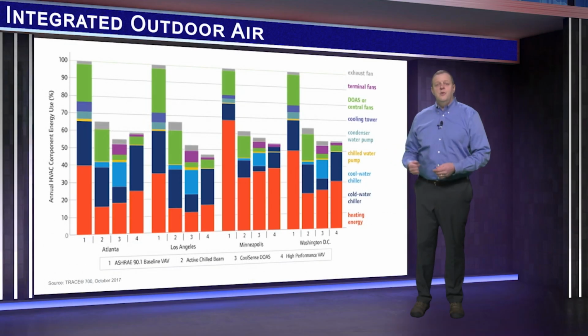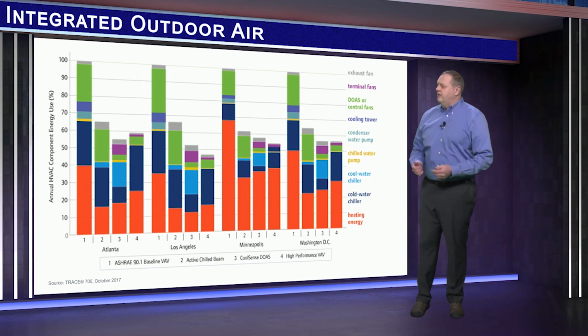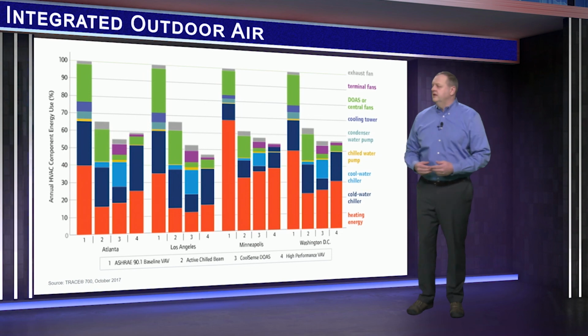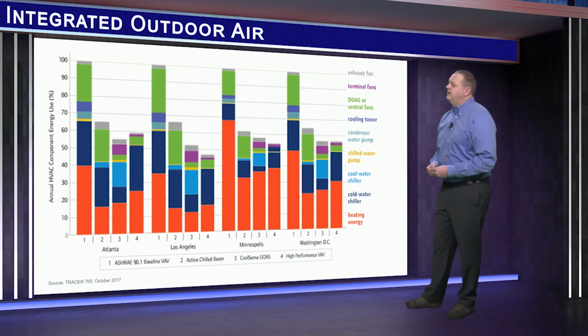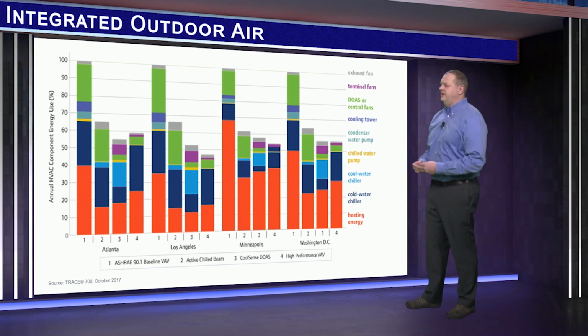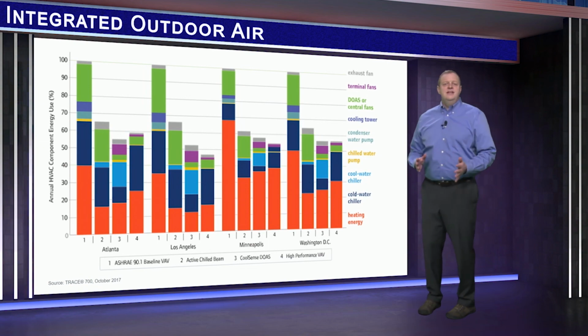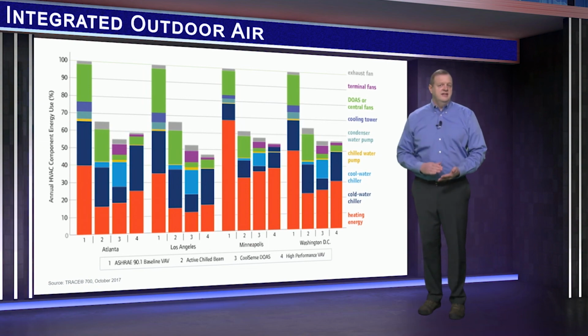Now in this chart, the y-axis is the annual HVAC energy as a percentage of the 90.1 baseline, which is the left-hand column for each of the 4 cities modeled. Now column 2 for each city is the active chill beam system. Column 3 is CoolSense, and column 4 is high-performance VAV. Note that each of the 3 systems use considerably less energy than the baseline.